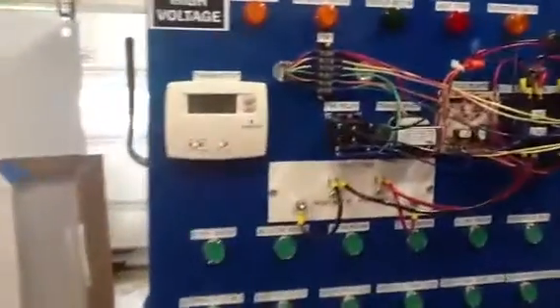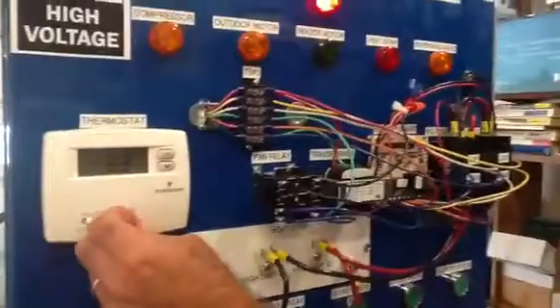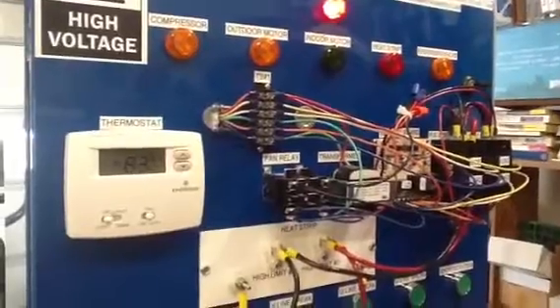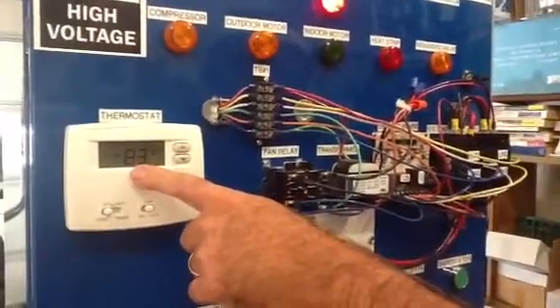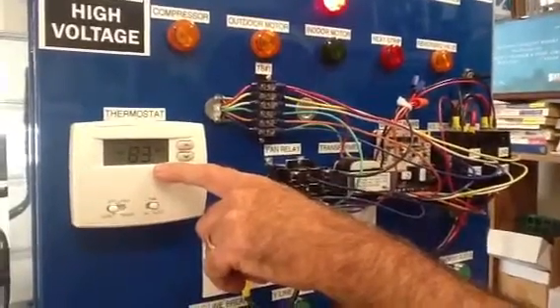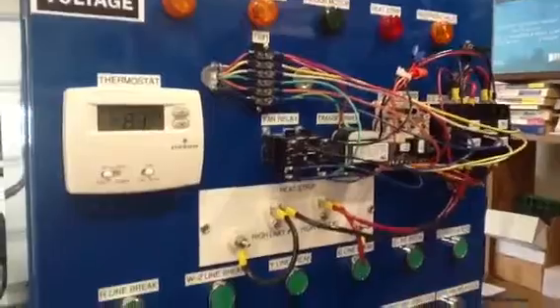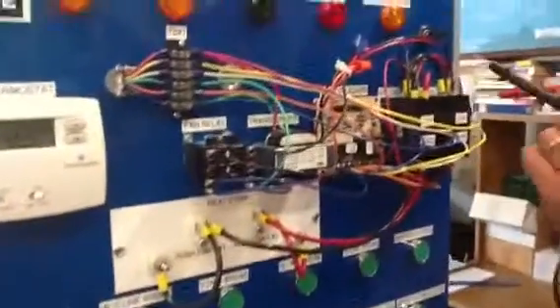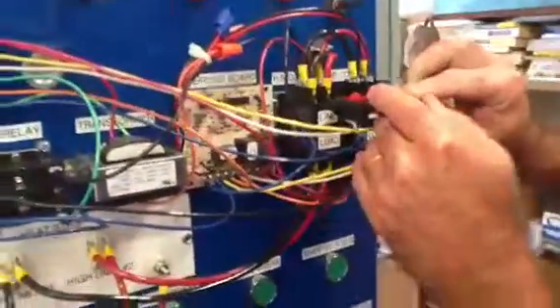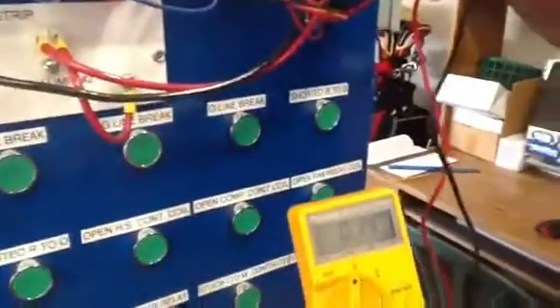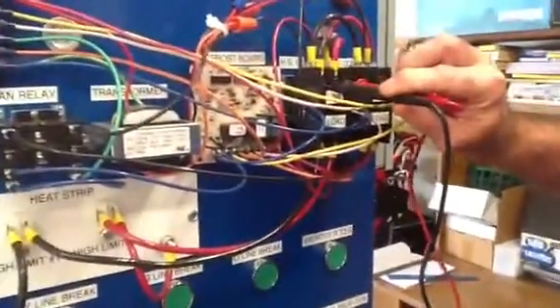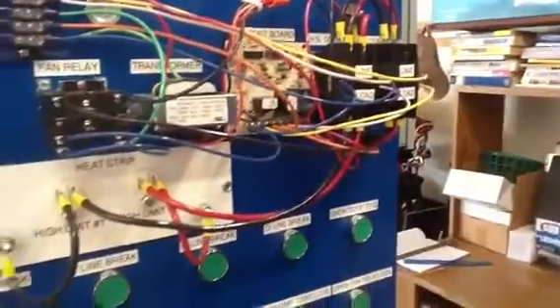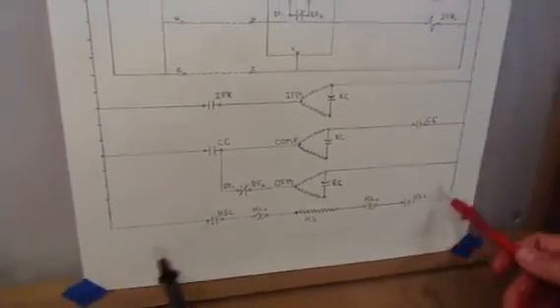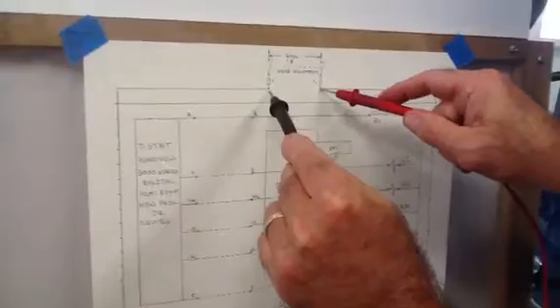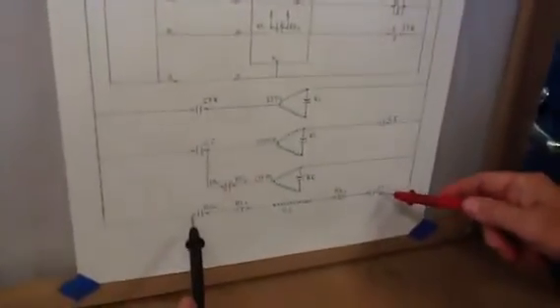Okay, so we're going to manipulate the thermostat. No indoor fan. 64 set point, 83 degrees. The snowflake is lit, no cooling. So what we're going to do is check high voltage, which will be the line side of the heat strip contactor, and we have 0 volts. Now these test terminals right here, I was at this point right here. I was here and here. And as you can see, line 1, line 2 of 240 volts. And I had 0 voltage at that point.